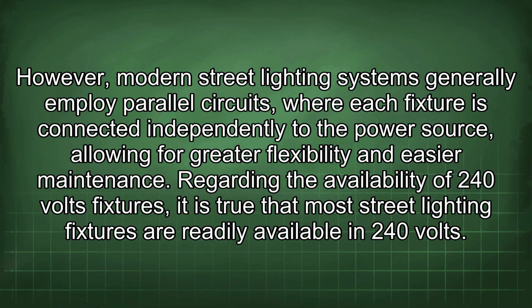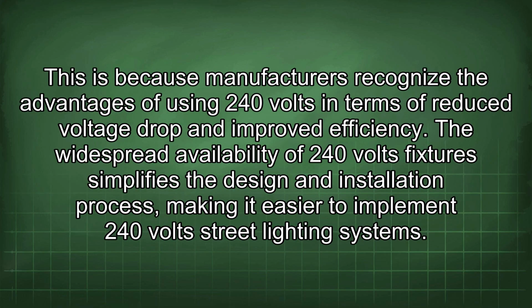Regarding the availability of 240 volts fixtures, it is true that most street lighting fixtures are readily available in 240 volts. This is because manufacturers recognize the advantages of using 240 volts in terms of reduced voltage drop and improved efficiency.